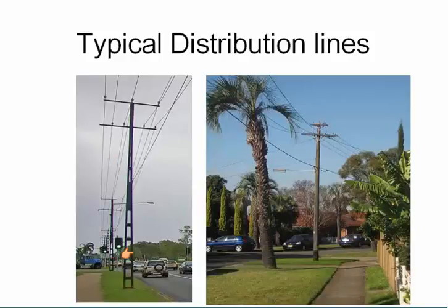These are not typical in a lot of countries, these types of concrete poles. The more common ones are timber poles. If you look at Australian statistics, there are millions of timber poles. I think 5 million timber poles. That's a fair bit. In New South Wales alone, there are more than 2 million timber poles. And timber poles account for 90% of the poles here in Australia. Similarly, United States, Russia, Europe, a lot of countries, timber poles would form the major chunk of the pole population. Timber poles, timber crossarms and so on. Concrete and steel are more expensive, less common.